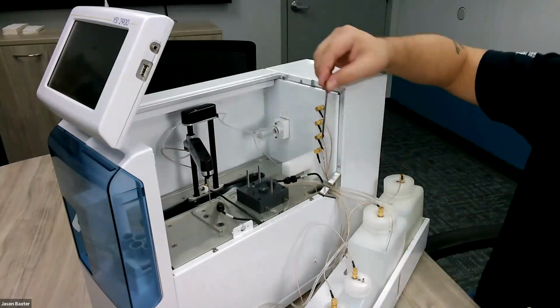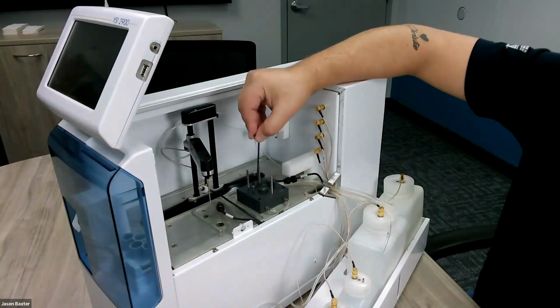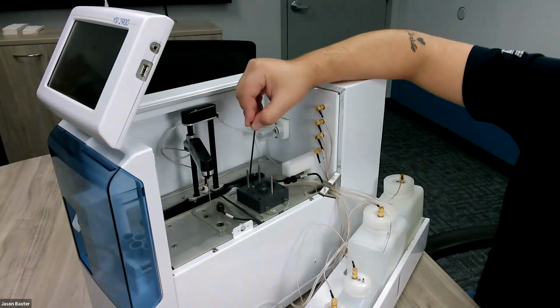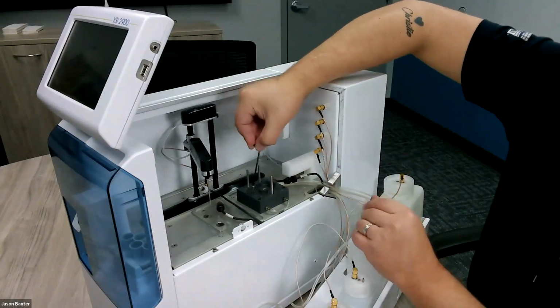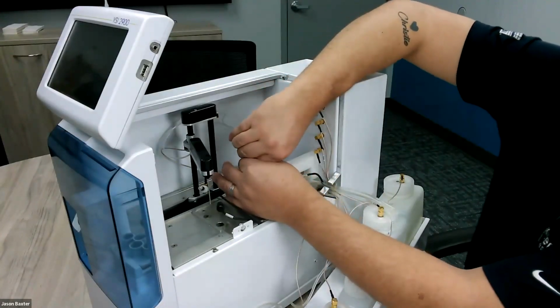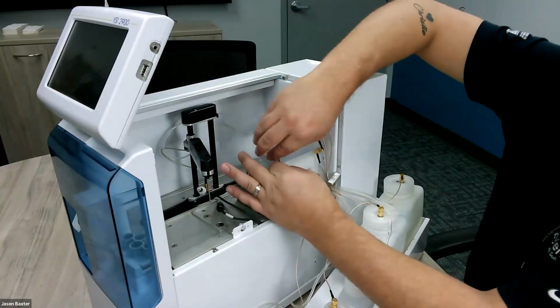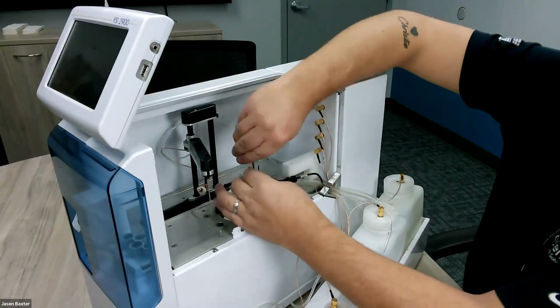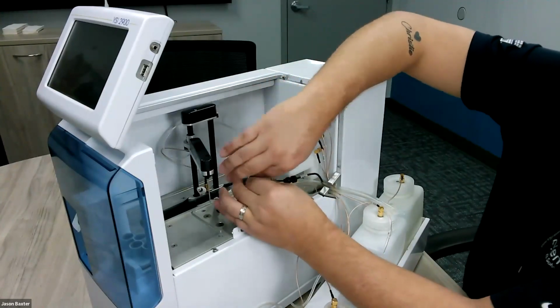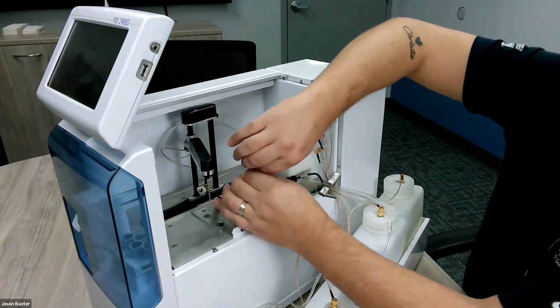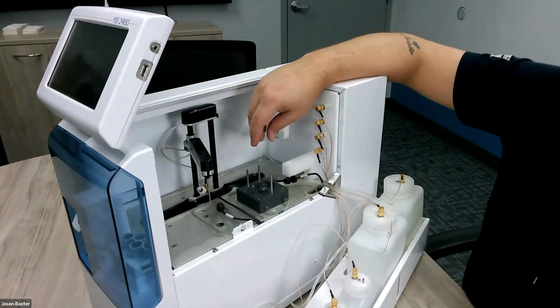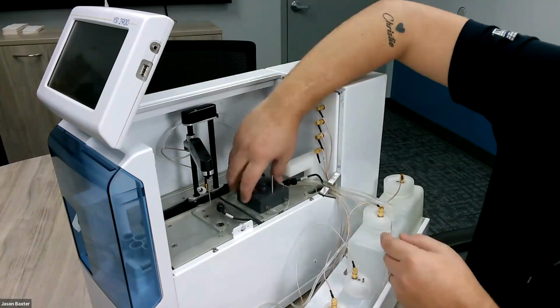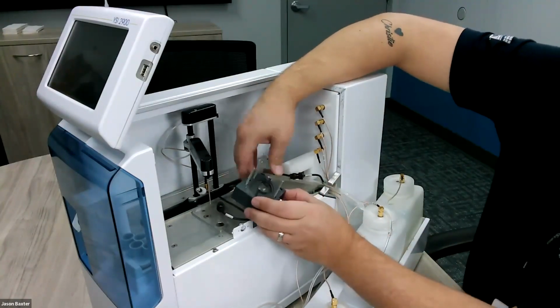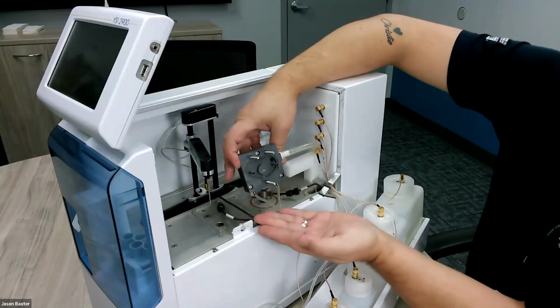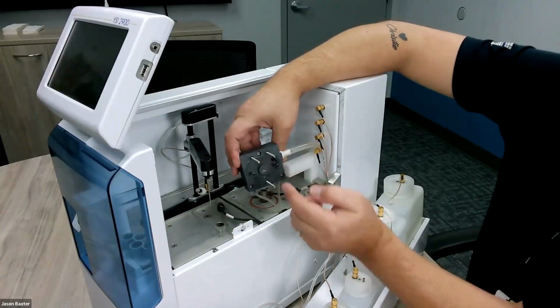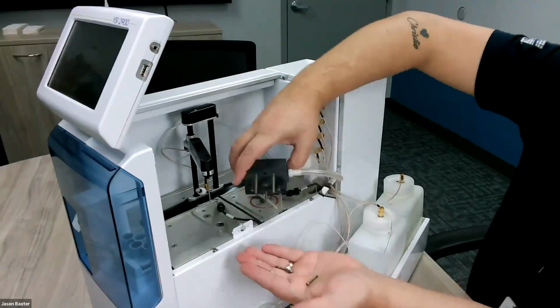Take your 3/32 Allen wrench and remove, there are a total of 3 bolts in here that hold the waste chamber down onto the deck. Once you have these 3 bolts removed, set them to the side. My personal suggestion is to set them very close to where you had the 3 wing nuts that hold the sample chamber on. So I'm going to tip this over and all 3 of these screws are going to fall out. So there we are.